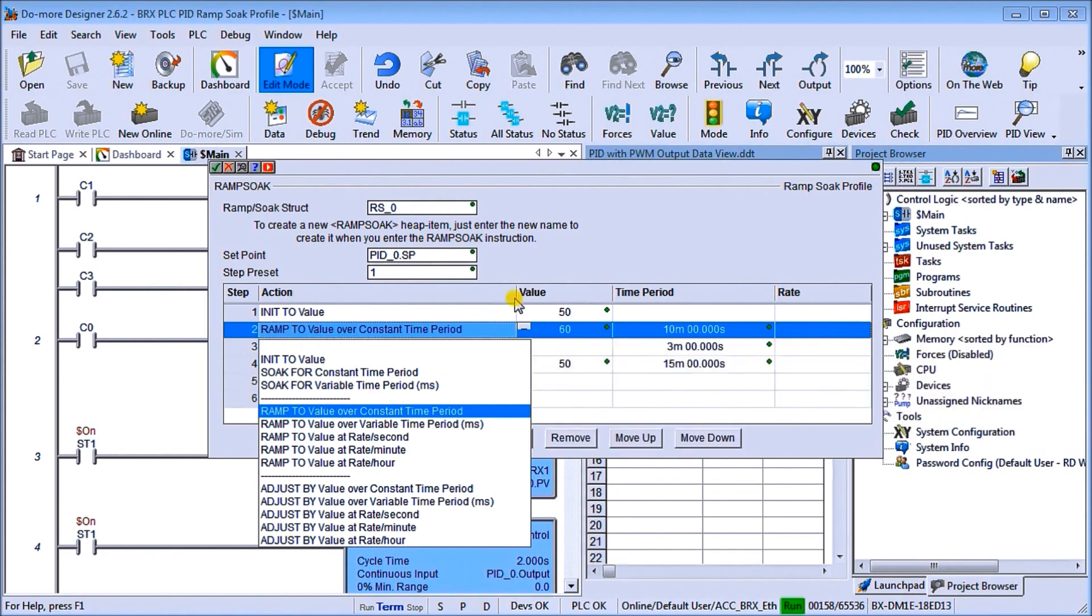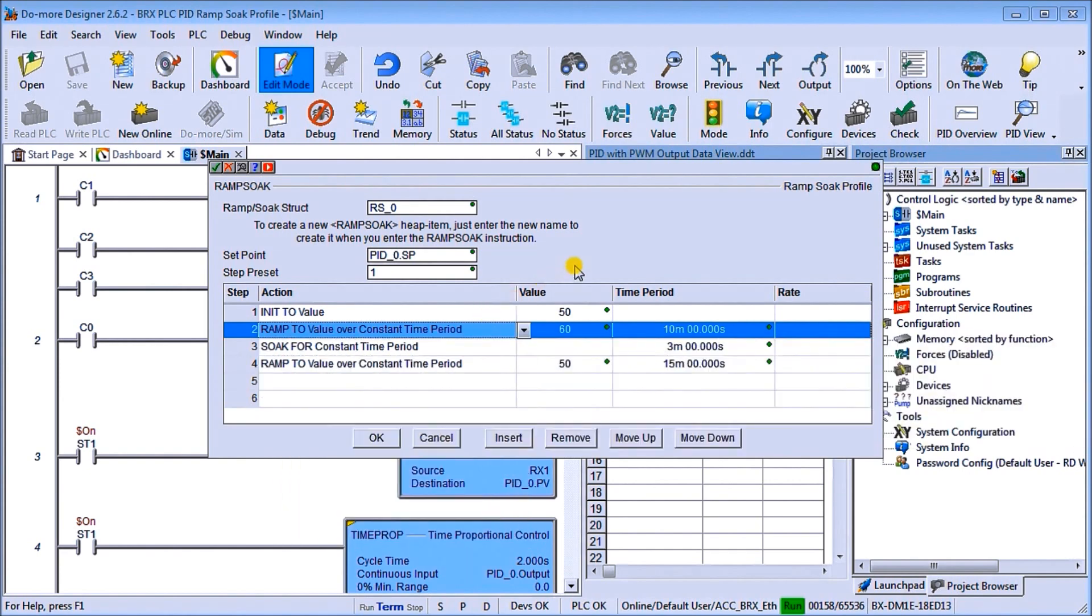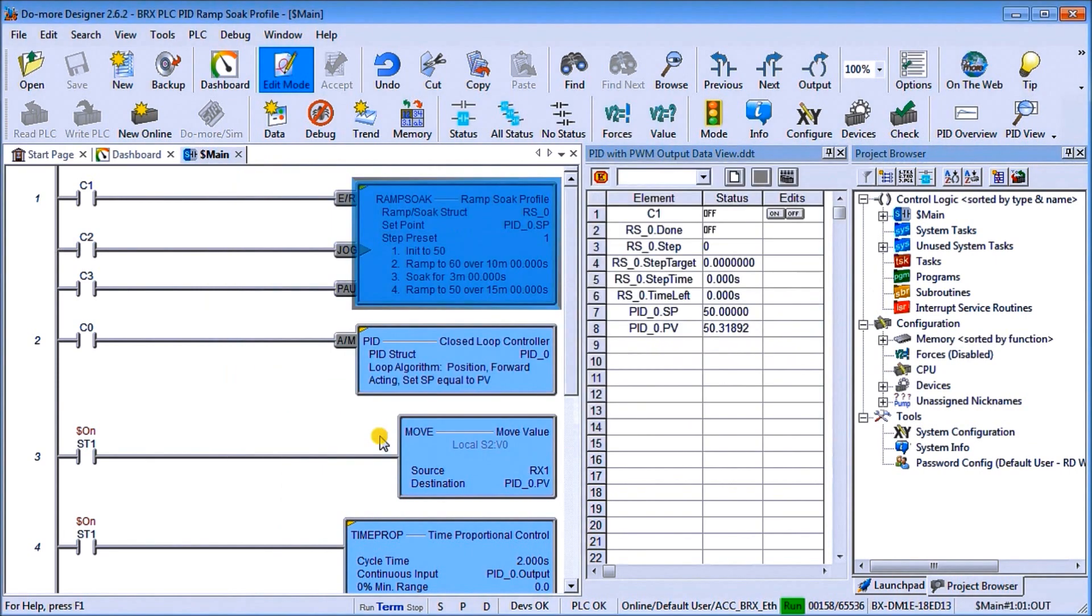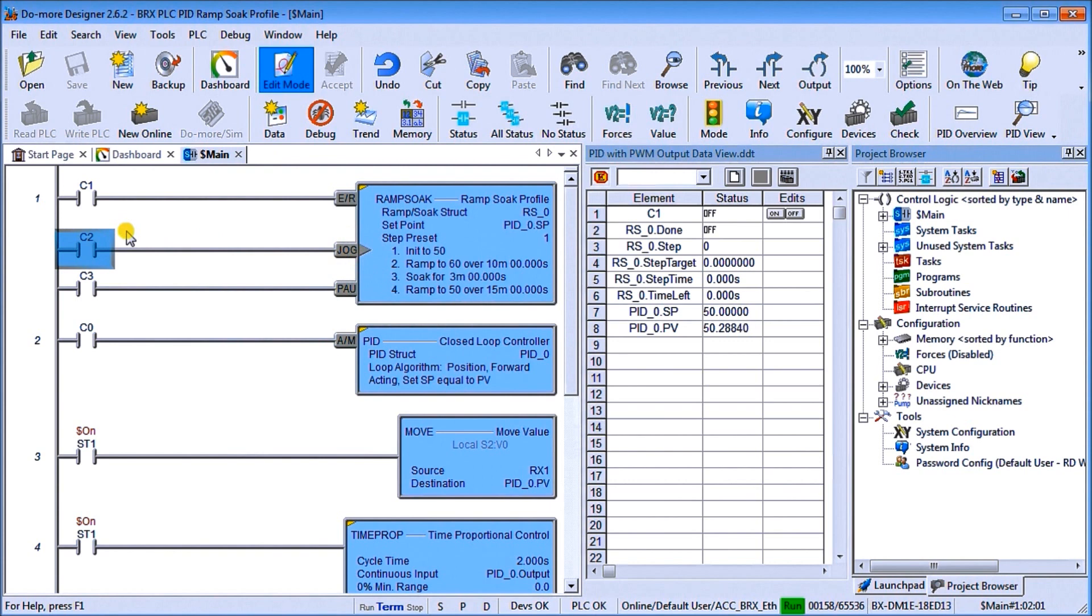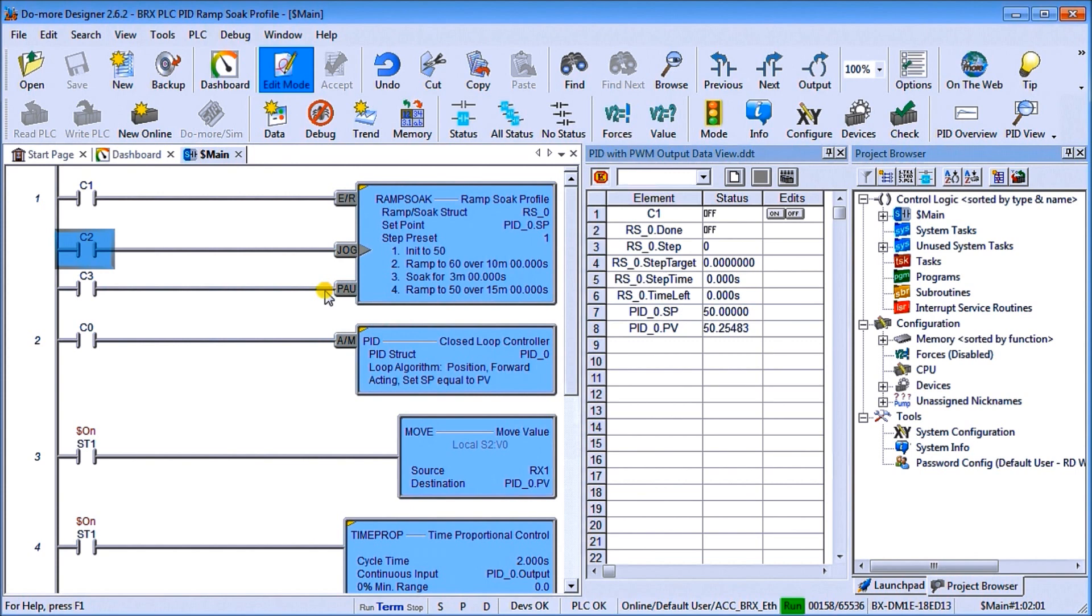So this is our profile that we have in our controller. Let's hit okay from there. And what you'll see is we have C1 and C1 will actually enable or reset our ramp soak profile. We have C2, which will have a jog and you'll notice that on C2, our jog is actually a one shot here. So we only do it once per cycle. And then we have C3, which is our pause. So we can pause this ramp soak feature that we have. So there are our different variables that we have.